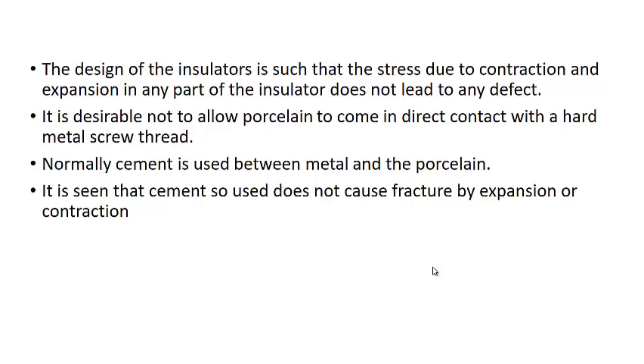Now coming back to the porcelain insulator, the design of the insulator is such that the stress due to contraction and expansion in any part of the insulator should not lead to any defect, because due to temperature change, if the temperature increases, it may expand, and if temperature decreases, it may contract. So it should be designed on that basis. It is desirable not to allow porcelain to come in direct contact with the hard metal screw thread, because in case of a pin type insulator, we have to insert a pin into the insulator, but that pin should not be in direct contact with the porcelain part. Normally, cement is used between metal and porcelain, and the cement does not cause any fracture by expansion or contraction. So that's why we use the cement.